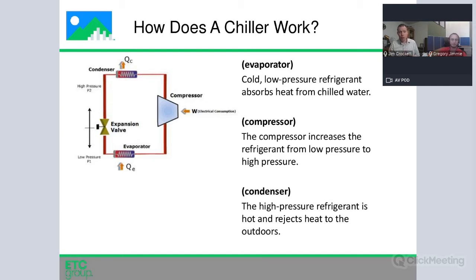So a chiller takes advantage of the refrigeration cycle. You've got the high side, which includes the condenser, and the low side, which is the evaporator. And so in a chiller, the evaporator absorbs heat from the building, and the condenser of an air-cooled chiller anyway takes that heat and rejects it out to atmosphere. When Greg talks to us about the water-cooled system, you actually have a water-cooled condenser instead of air-cooled. Let me start with the evaporator. So the evaporator is the low pressure side of the system. The compressor raises the pressure up to high pressure for the condenser, and it remains at high pressure until it goes through the expansion valve.